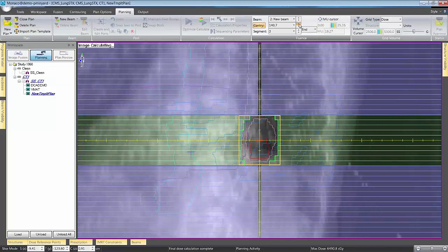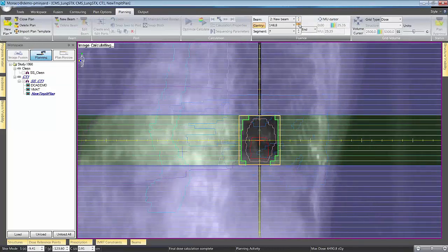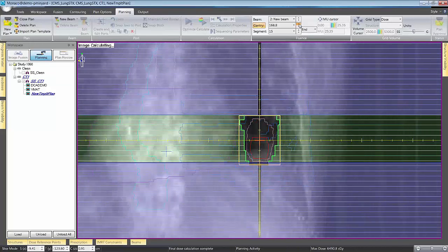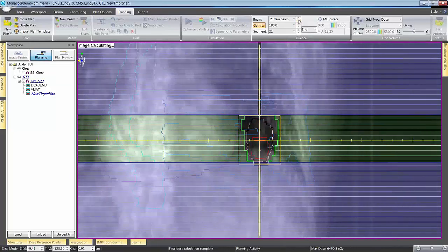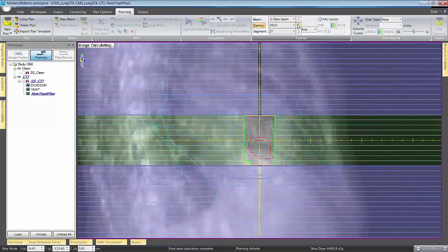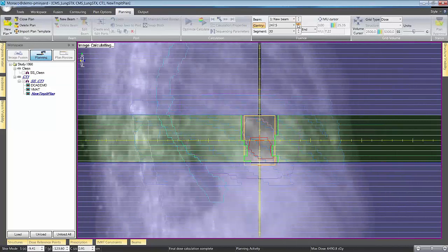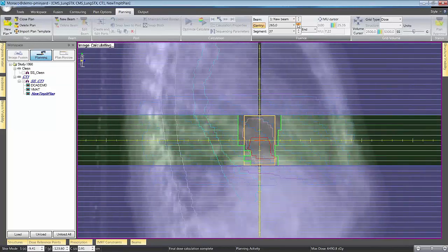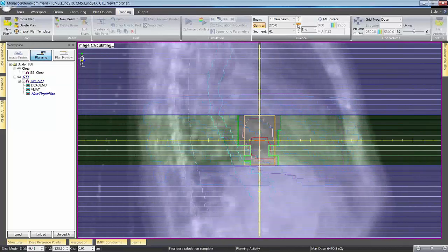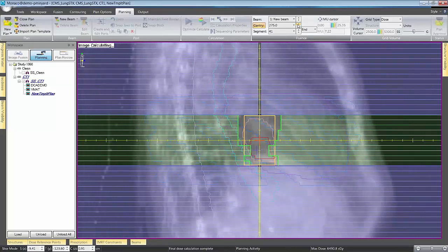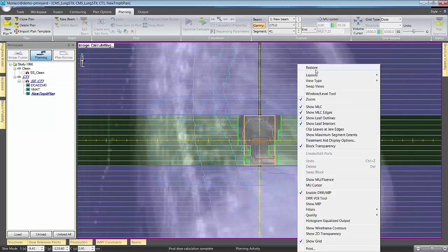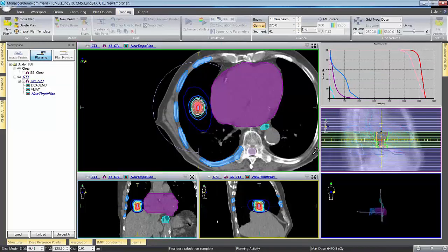Again, just on the edges, not a lot of movement on this one, keeping it nice and tight. And back to the first beam, just to show you some of that modulation. Obviously with VMAT, you're going to have more modulation because that's the whole point. But a little bit of modulation on the edges with DCA actually gives you a tight conformal plan.